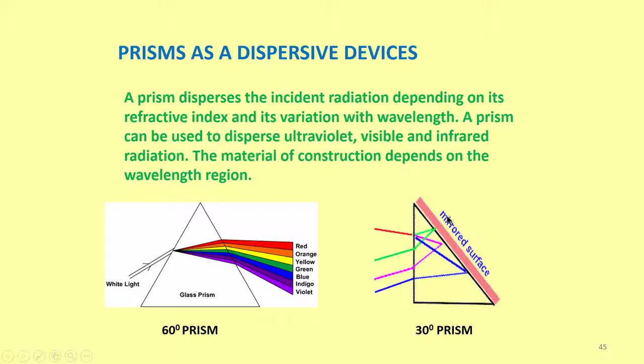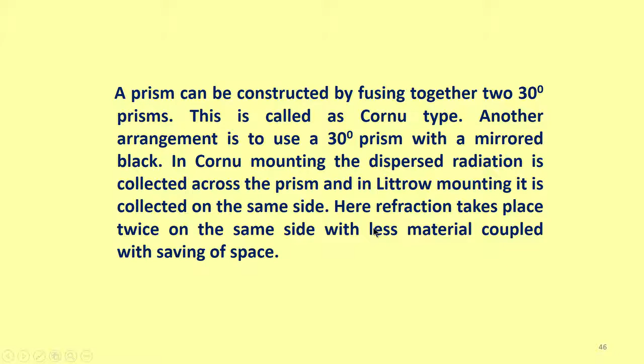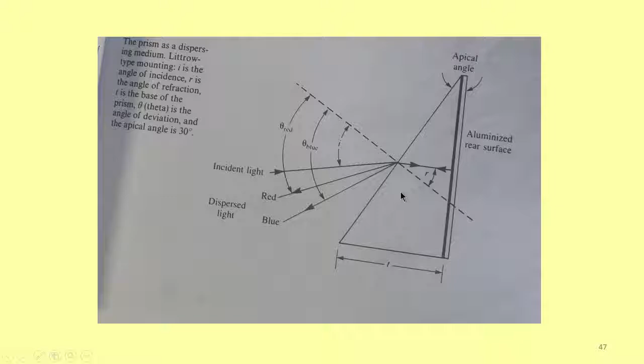A prism can be constructed by fusing together two 30-degree prisms. This is called Cornu, that is 60 degrees. Another arrangement is to use a 30-degree prism with a mirrored back. In Cornu mounting, the dispersed radiation is collected across the prism, and in Littrow mounting it is collected on the same side. Here the refraction takes place twice on the same side with less material, coupled with saving of space. So, this is Littrow mounting. This is taken from Willard, Merritt and Dean, which I have given as reference.